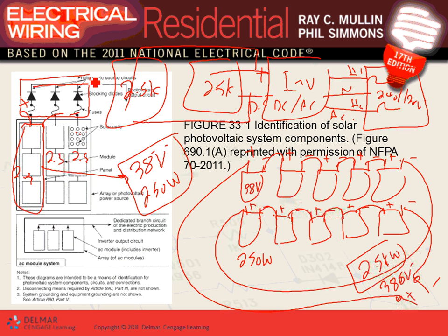Can you see these diodes here? These diodes, they put them in the circuit so a panel cannot feed another panel. So if you have a short circuit in one panel, you don't feed the energy right through it. You studied diodes. I don't know if you did, but you guys studied diodes. Diodes are valves. They allow the current to go one way, not the other way. So by putting a couple of diodes here on the strings, they can direct the current away from the modules, not into the modules. Who cares? If you have a short circuit in this module, guess what? If you don't have this diode, the current will come here, bang, and cook that panel. Now you're burning another panel, another string next to you. So the smart ones put a couple of diodes to control the flow.